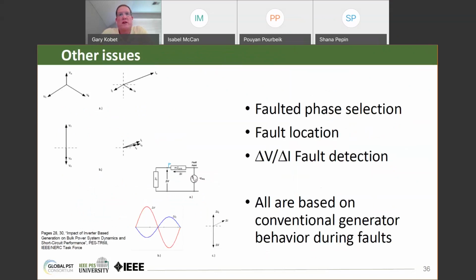Some other issues: faulted phase selection, fault location, fault detection. All these methods are based on conventional generator response during faults. This is typically called a voltage behind impedance model for the synchronous machines. If that is not true of IBR, then phase selection, fault location, and fault detection may not work as intended.